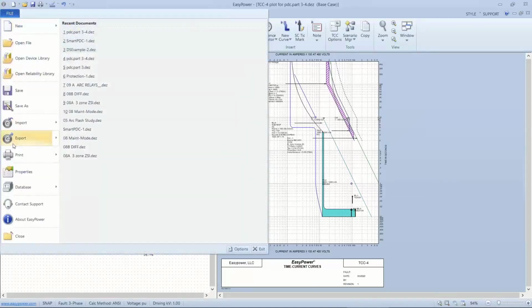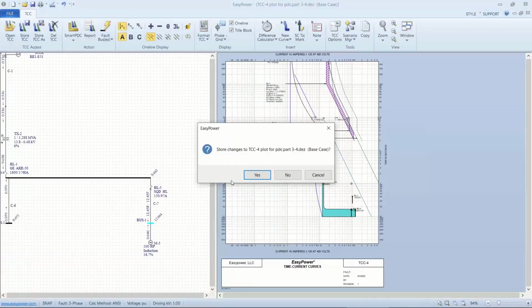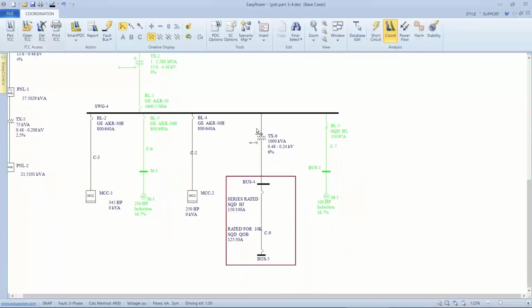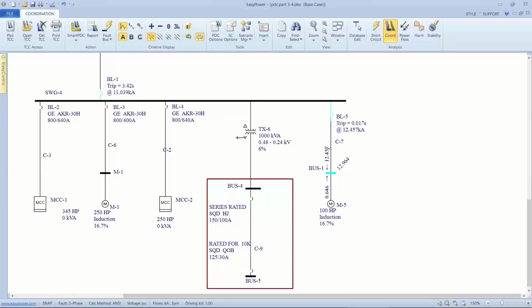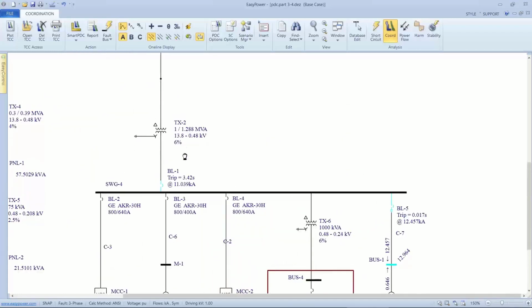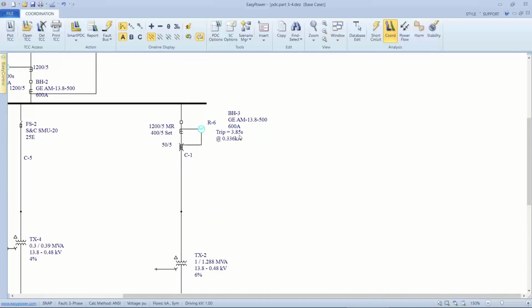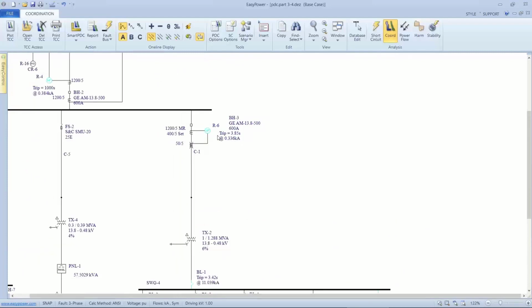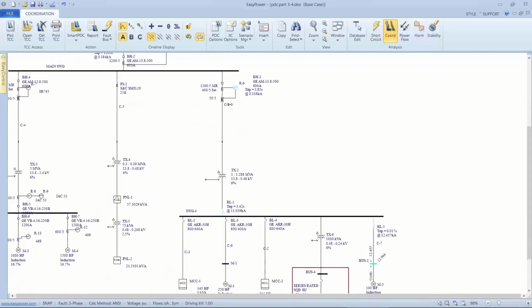So let's go back. One more check that the tool has in it that can be very useful is what's called sequence of events. If I'm in coordination, pick out a downstream bus, fault a single bus looking at current, the plot will show me, the one line will show me the current for that particular fault. It would also let me illuminate the sequence of events icon. And now instead of current, it's showing me the trip time. So if this bus faults, this breaker trips in 17 milliseconds, this breaker trips in 3 seconds, and the relay will trip in 3.8 seconds. So I do have coordination for a downstream fault.